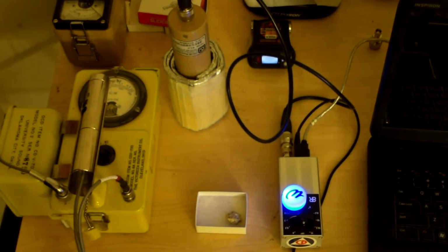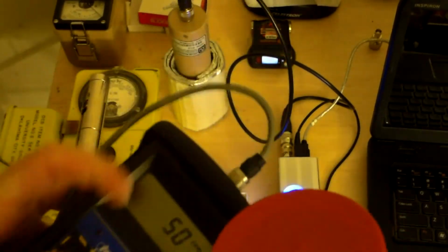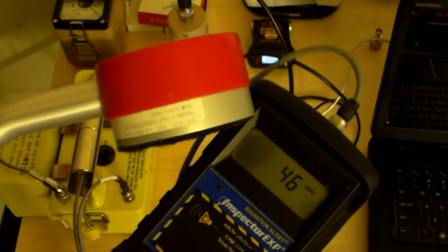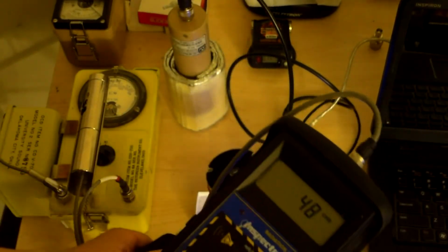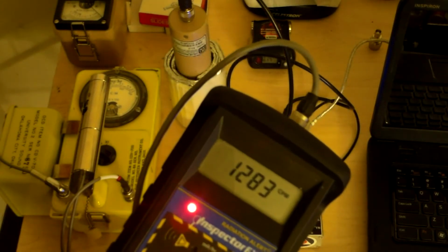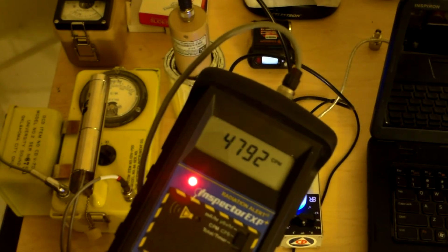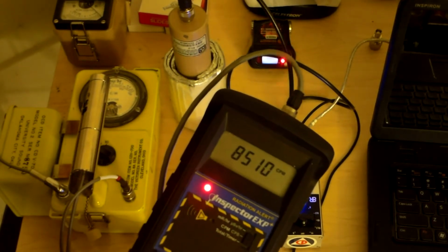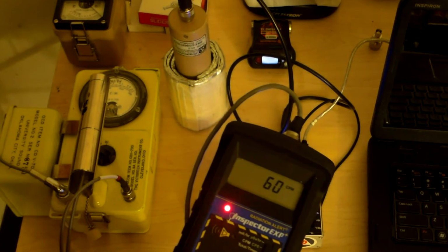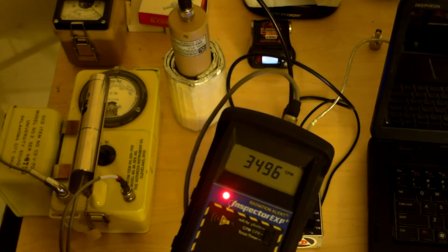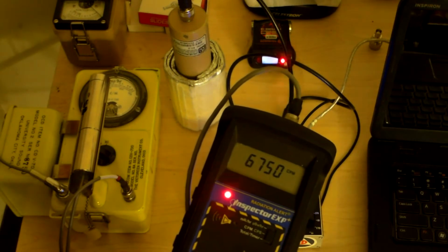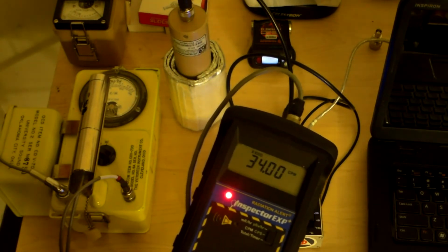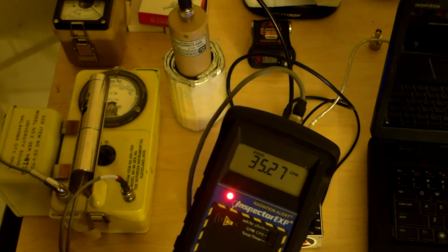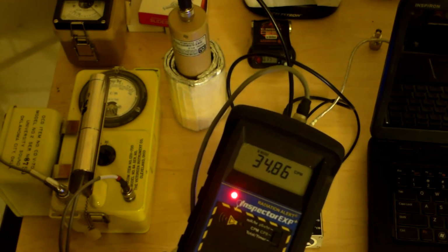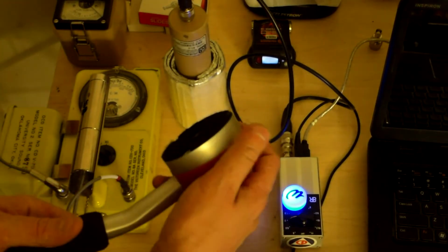Not bad. And in fact, with an inspector, it's not exactly a beta shield. It definitely shields alphas and low energy betas. But with this shield in the front of it, let's see what I get. That was neat. 60? Talk about a fail, huh? There we go. 35,000 counts per minute. 34. About 35,000 counts per minute.